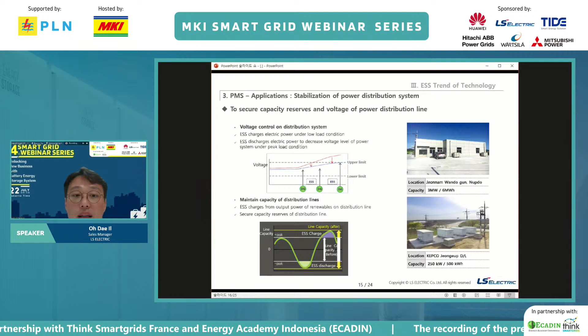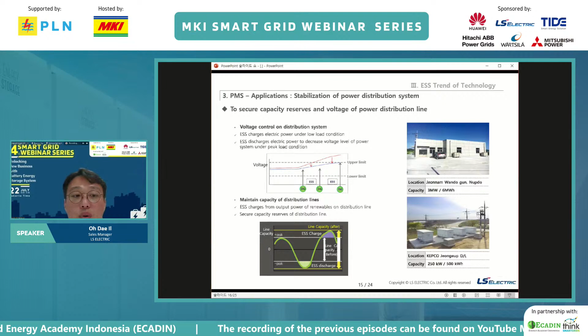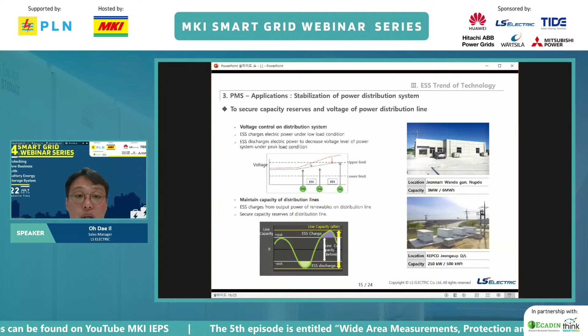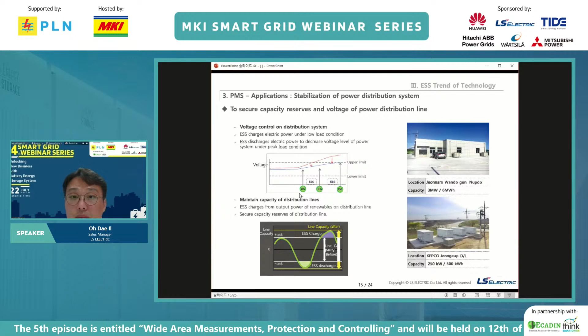Voltage control on the distribution system is an additional feature in ESS. It secures capacity reserves and voltage of the power distribution line. ESS discharges electric power to decrease the voltage level of the power system under peak load conditions, and charges electric power under low load conditions.